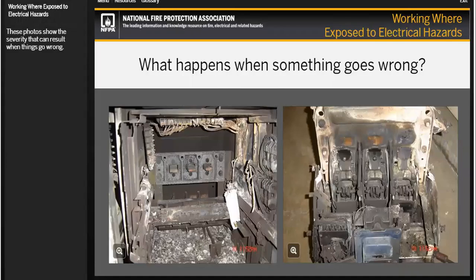Overloading comes under NFPA 70E because the equipment is designed and installed for some specific load condition. Now how you are overloading, how you are interacting with the equipment - if you go above its rating, that comes under NFPA 70E, electrical safety at the workplace.